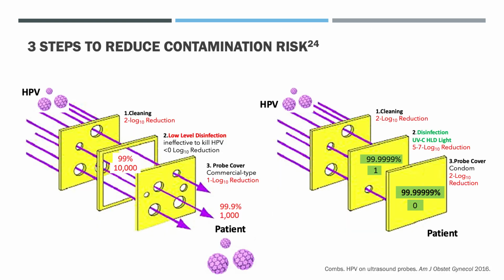Again, steps to reduce contamination for HPV: cleaning, low-level disinfection, and probe cover. You can see here that you have only 99.9% removal at best. And so if you have enough patients, clearly there are going to be patients in whom this method will lead to contamination and infection. Whereas on the right, if you use a high-level disinfection, such as with ultraviolet light, you're adding cleaning 2 logs, which is really 2 to 4 logs in many cases, disinfection 5 to 7 logs, and then additional protection with a probe cover, which really gives you a 0 risk for the patient.